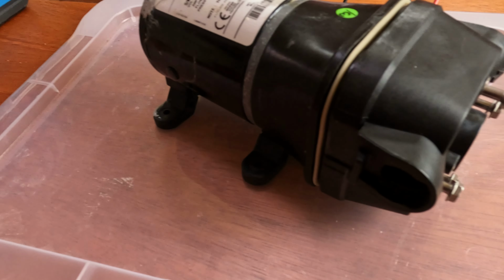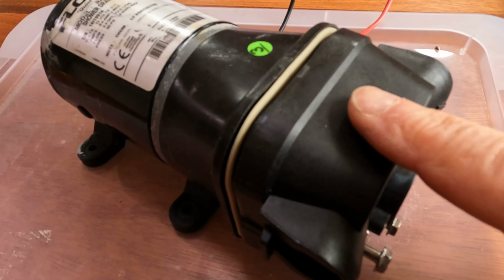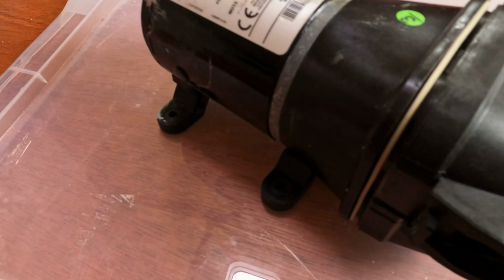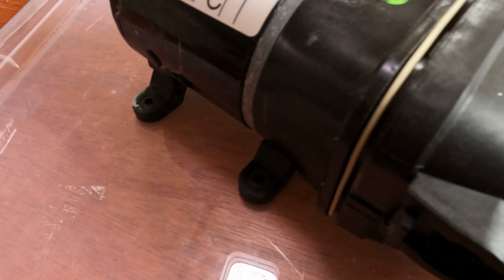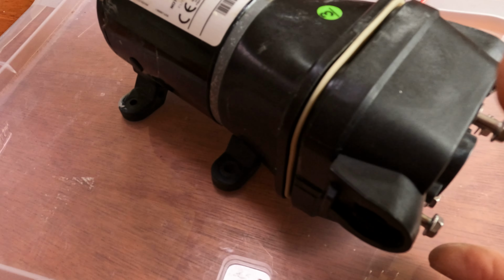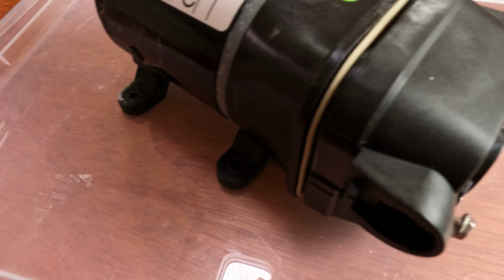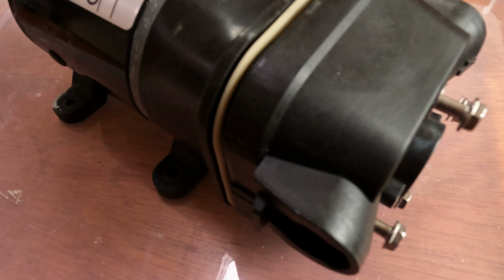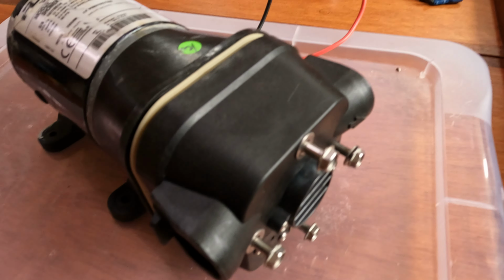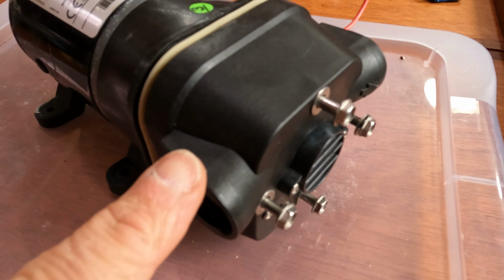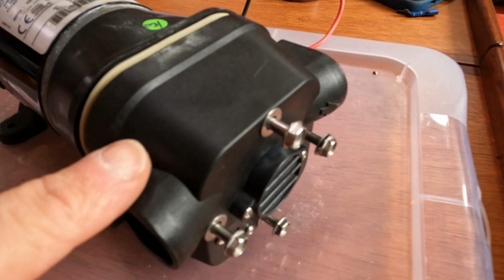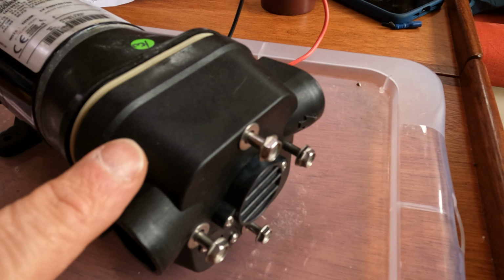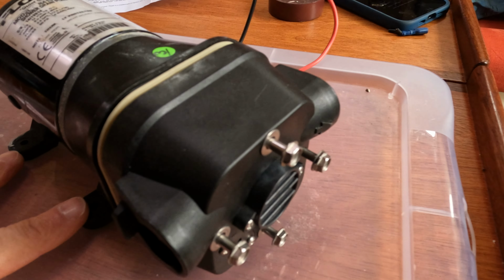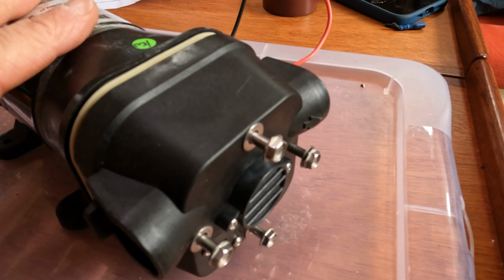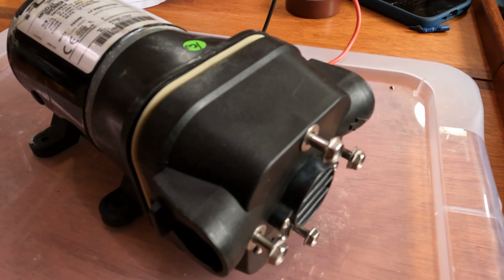So one trap for the unwary when reassembling the head onto the body is to ensure the ports are correctly aligned. Obviously if you have it, it'll fit together rotated through 90 degrees, but if that doesn't match your hoses, and particularly if you're in an enclosed space where it's fitted, it won't work. So you need to make sure the pipe connectors are aligned with the mounting points on the motor. This definitely didn't happen to me.